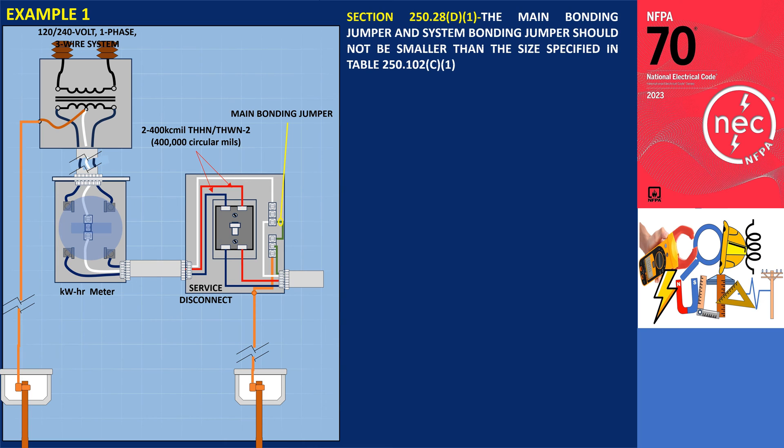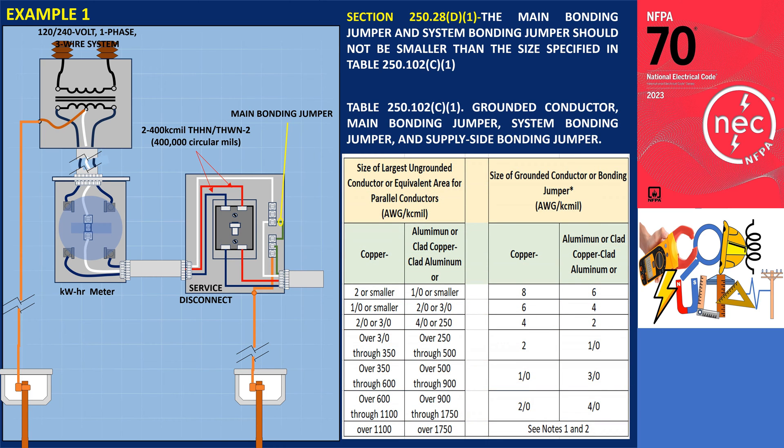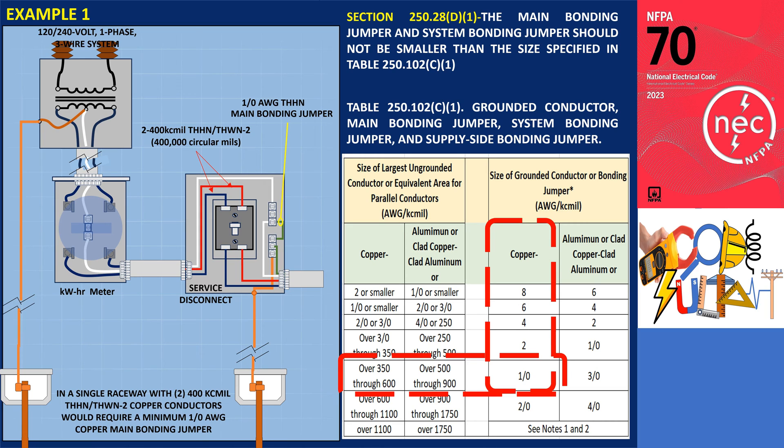According to 250.28 D1, the main bonding and system bonding jumper conductors should not be smaller than the size specified in table 250.102.C1. Since our conductors are 400 kcmil copper, we locate the row that states 'over 350 through 600' on the left side of the table under the copper column. As our example falls within that range, we move horizontally to find that the recommended size for our 400 kcmil conductors is 1/0 AWG.